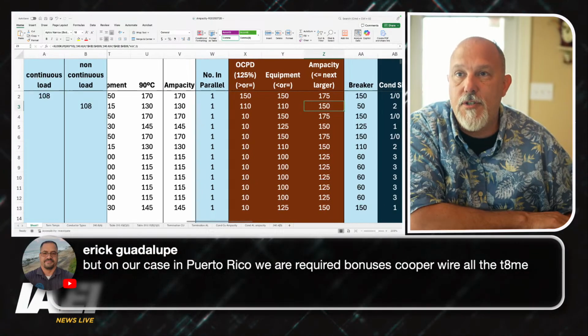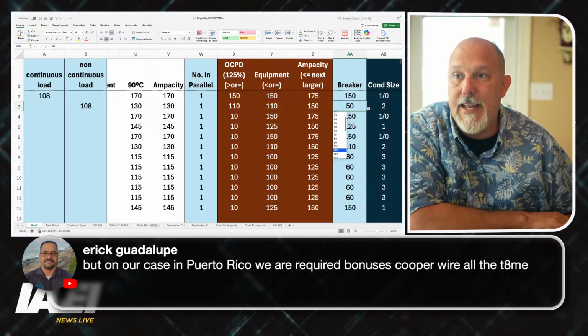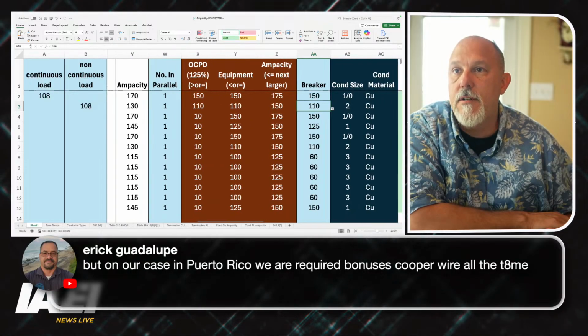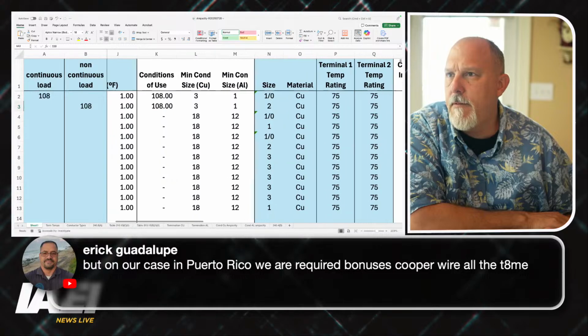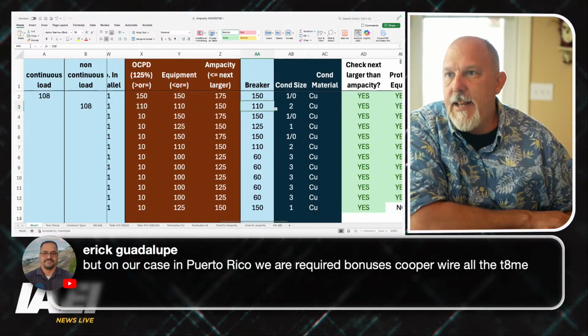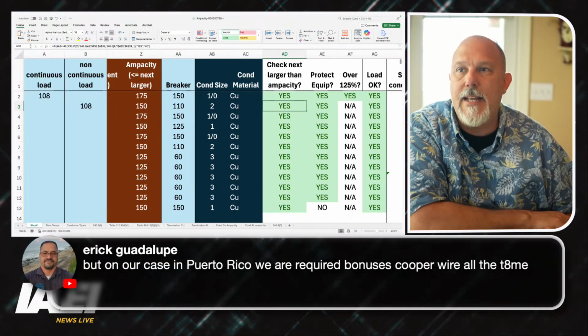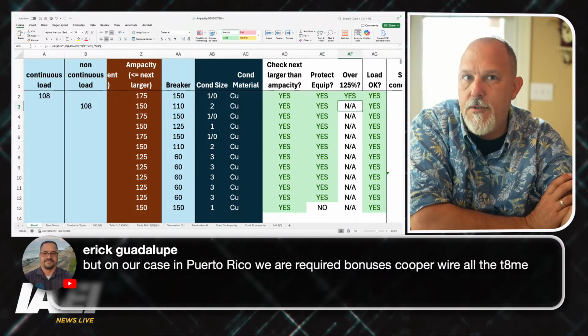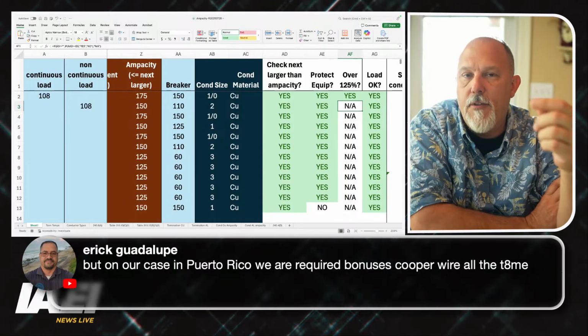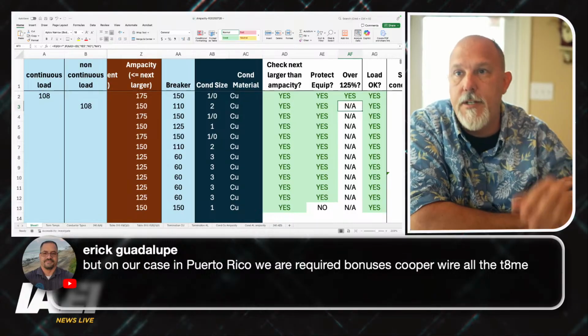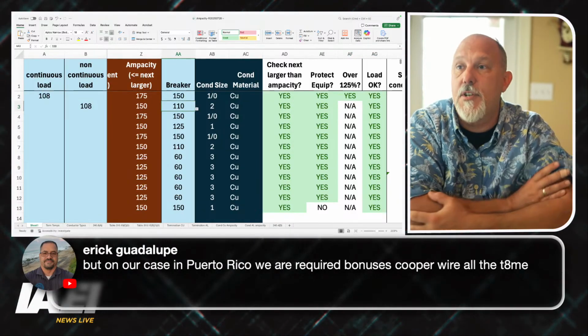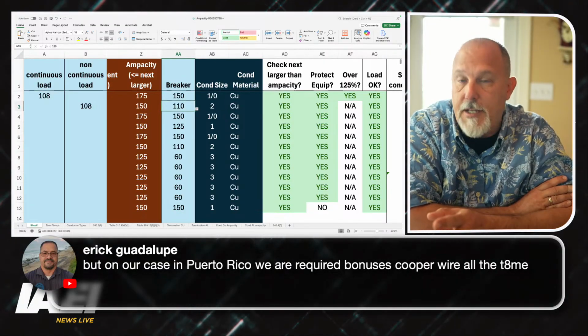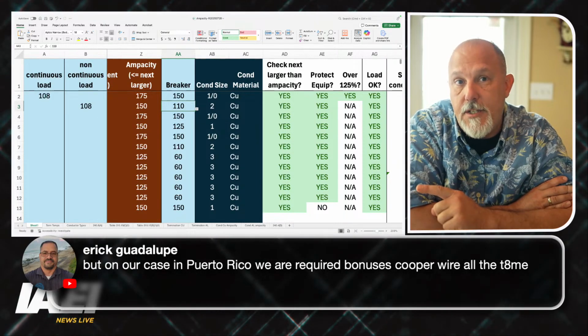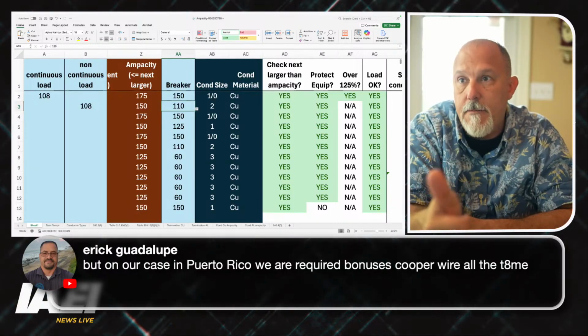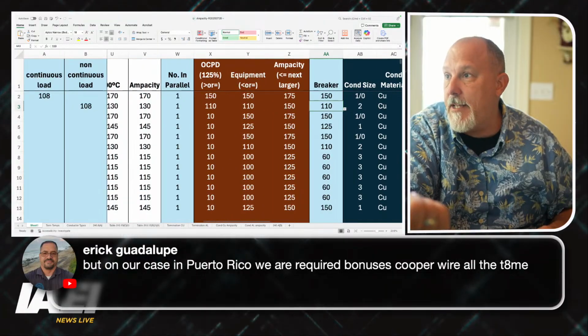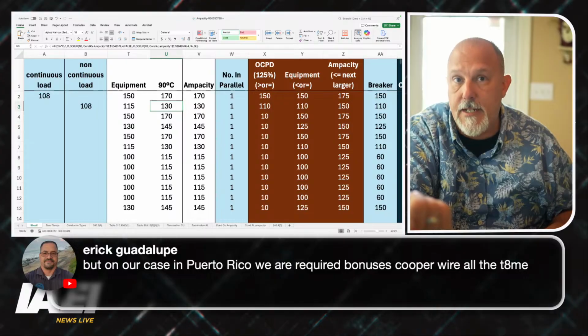My ampacity of the next larger is 150. So if I pick a 110 amp breaker to protect a number 2 gauge, do I got that right? Yep. If I have a 110 amp breaker to protect a 2 gauge, I am good on ampacity. I'm good with equipment. I don't have a continuous load, so I don't have to worry about being greater than 125%. I just have to be greater than the load current, which is fine. So a 110 amp circuit breaker would work perfectly fine for this application with 108 amps of a non-continuous load. I meet all the rules. I'm protecting the equipment. I'm protecting the conductor, because the conductor's ampacity is 130 amps, and a 110 amp breaker is going to protect the conductor at its ampacity.